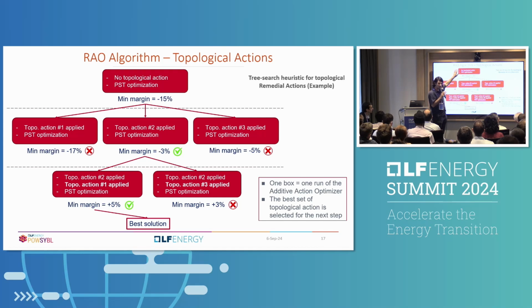Then we optimize the PSTs. As Nicolas said, we basically use a mixed integer linear program. In this case, after optimizing the PSTs, we get a minimum margin of -15%, meaning the most overloaded line is overloaded by 15%. This is the value which is interesting for us, and we want to maximize it as much as we can. So this is the first step.